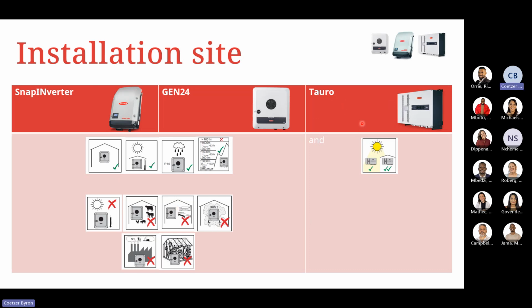Whereas the Tauro, for example, this unit is designed to withstand the elements. So it is designed to sit directly in the sunlight and have no effect on the heat soak from the unit itself. We get away with this with the twin wall cooling that we have on the unit itself. So again, we do recommend trying to install it in a shaded environment, but if not, you can install it in direct sunlight.